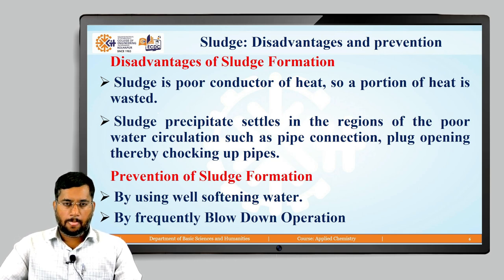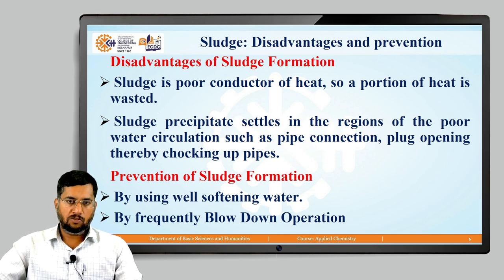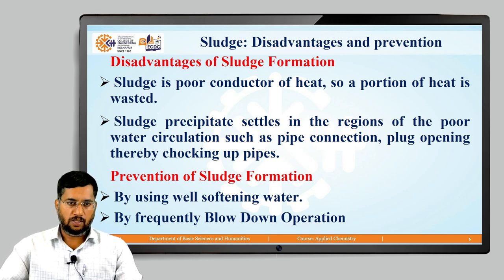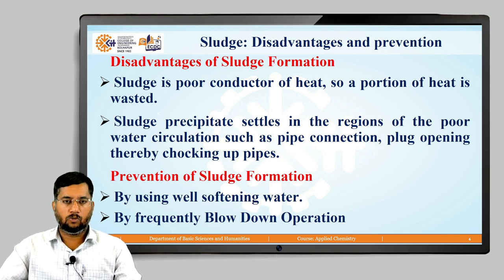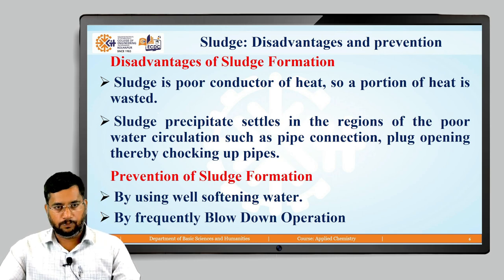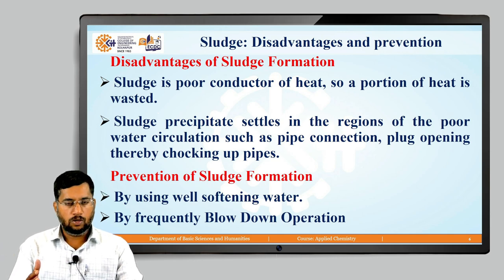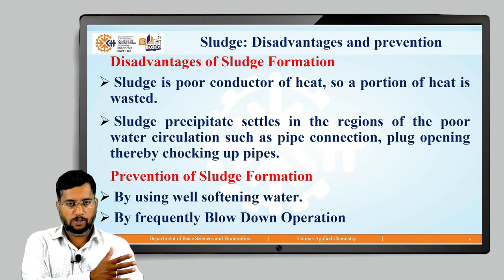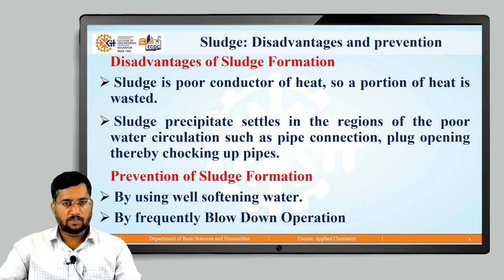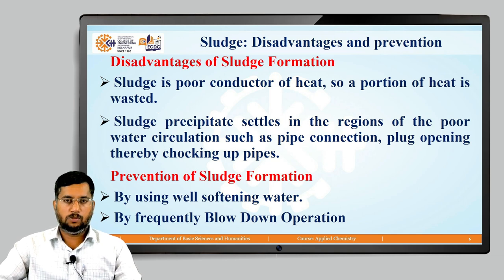To prevent sludge formation: before feeding water to the boiler, remove dissolved impurities using various water softening processes. Also, frequent blow-down operations — a sudden flow of water — can remove the loose and slimy sludge precipitate, which typically forms at the colder portions of the boiler.